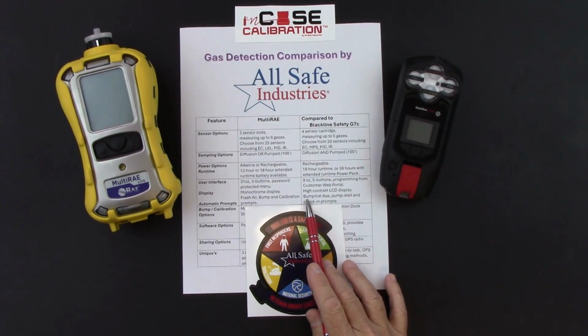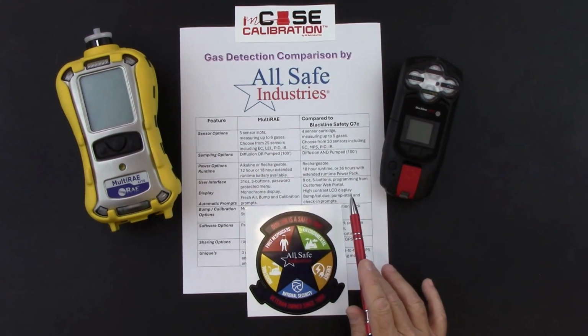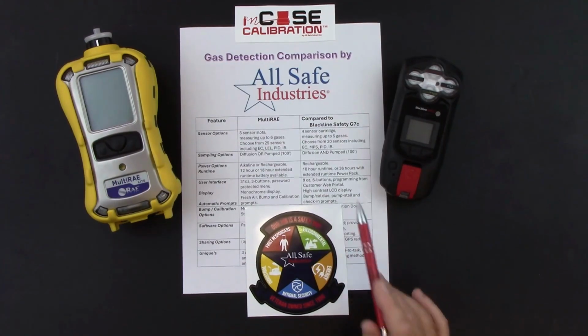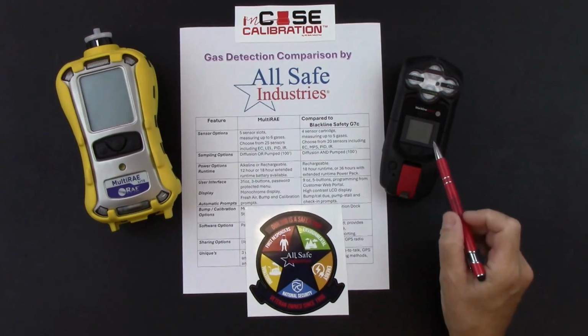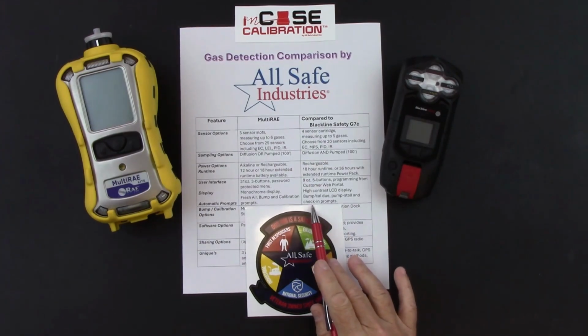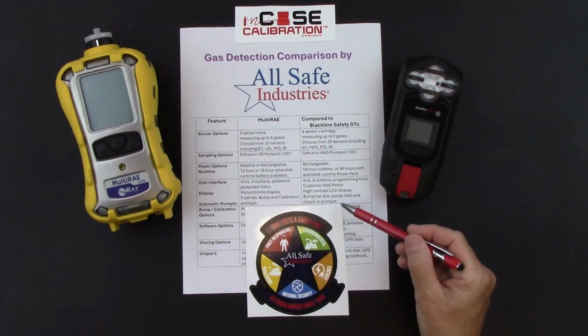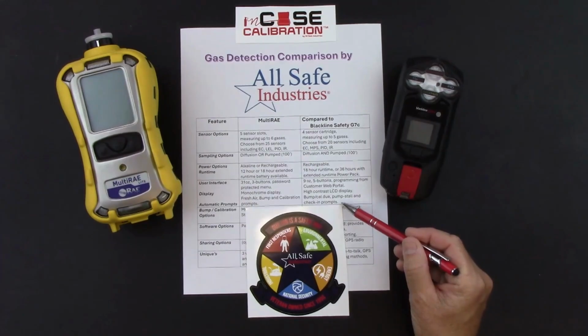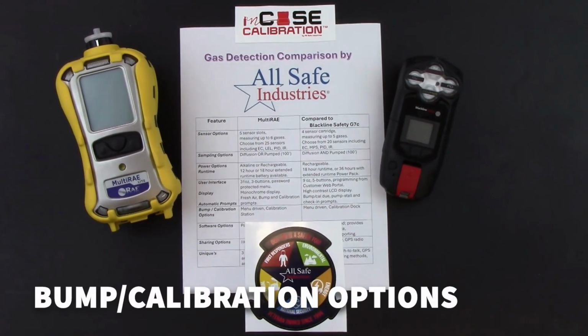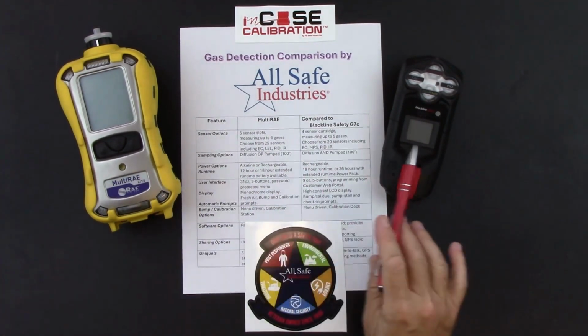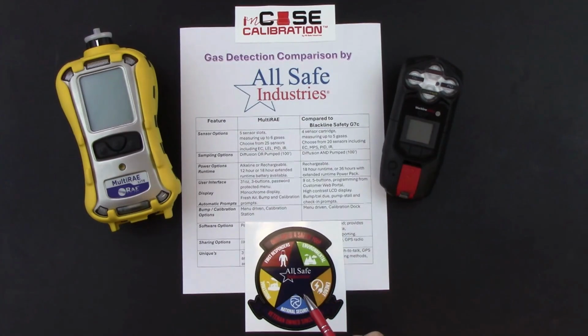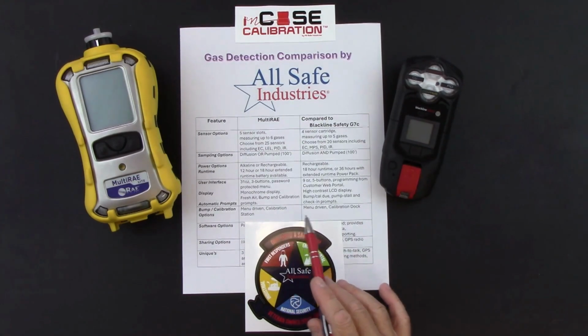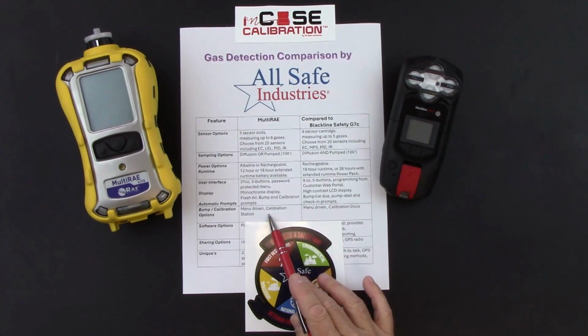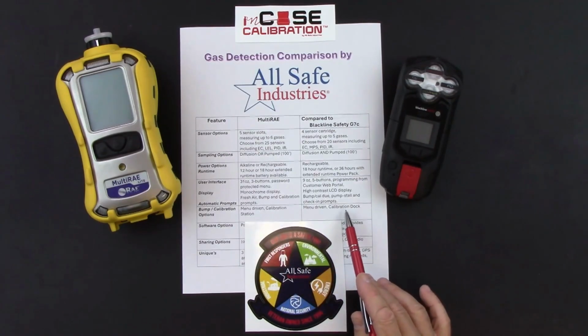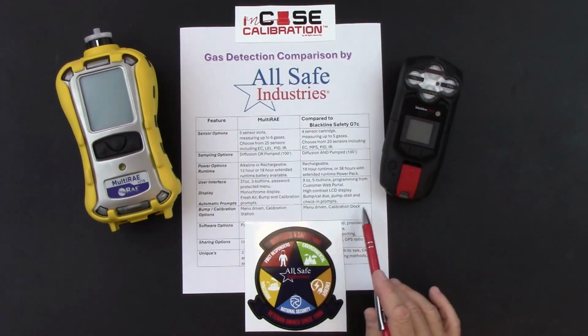It will prompt you when a bump or a calibration is due, and when you activate the pump, it's going to ask you to do a pump stall to confirm that the pump is working properly. You can also program the G7c to prompt check-ins from your user. This is especially useful in lone worker situations. For bump checks and calibrations, you can process both of those through onboard menus on the instrument, but you can also run these through the calibration stations, the AutoRAE 2 for the MultiRAE or the Blackline dock for the G7c.